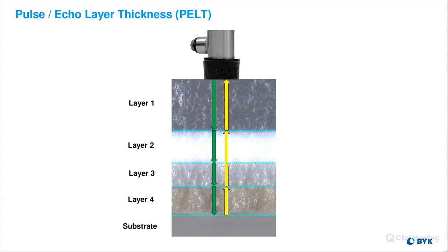Another mistake we see a lot is that sometimes we can trap a little bit of water or a dirt speck between the cap and the top of our clear coat, and it gives a wider, crazy-looking echo in the front. We tell our customers to slow down, move over just a half of a millimeter, and make sure that front echo is as clean as possible with the least amount of noise. That will give you the best waveform possible. Some of our old timers, when I say 3 to 5 seconds, that might seem like an eternity.